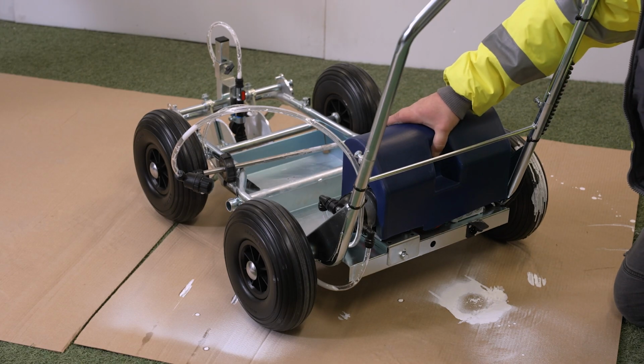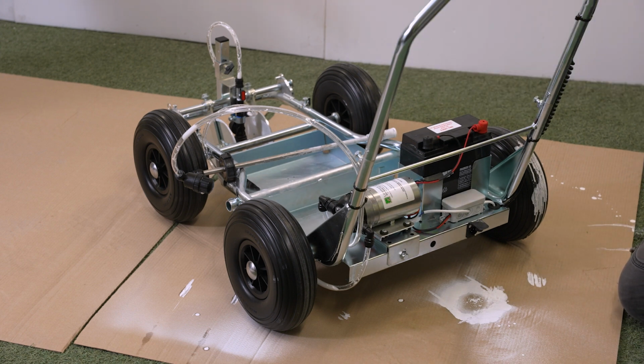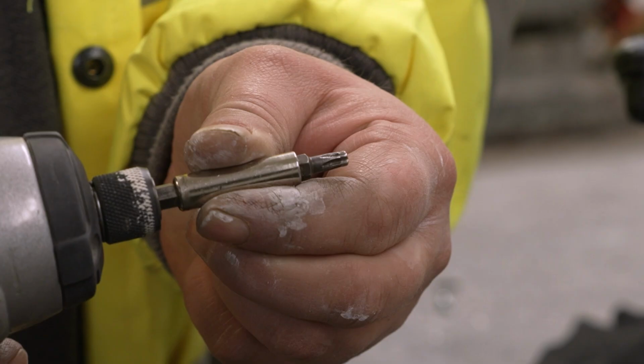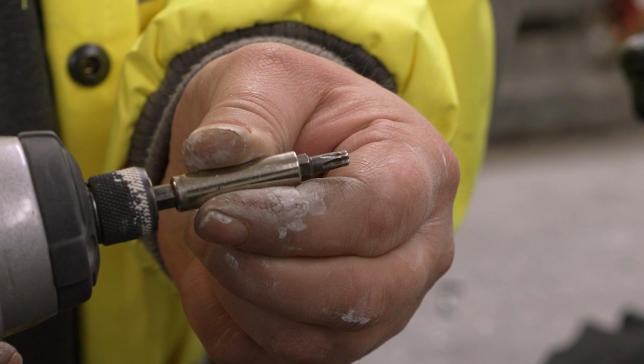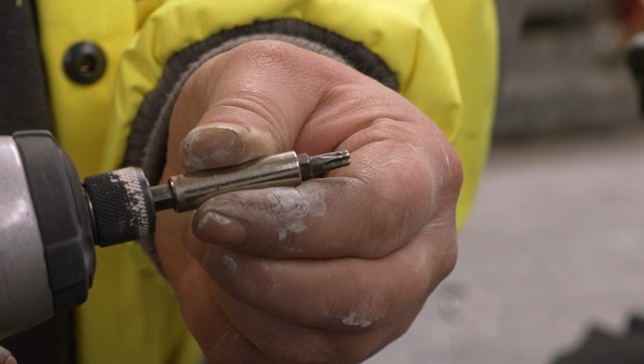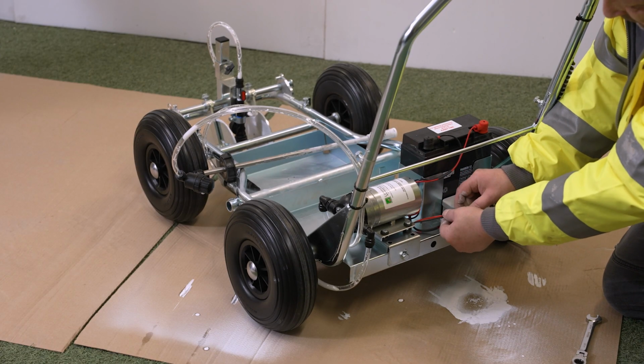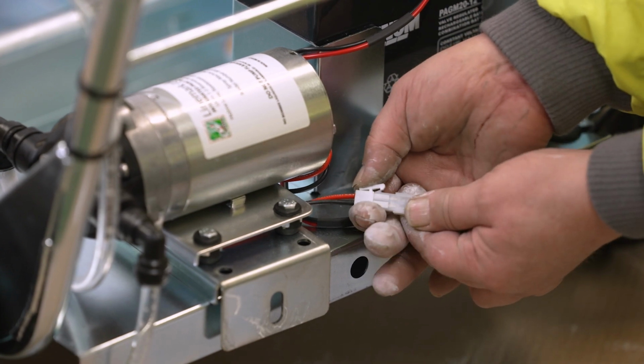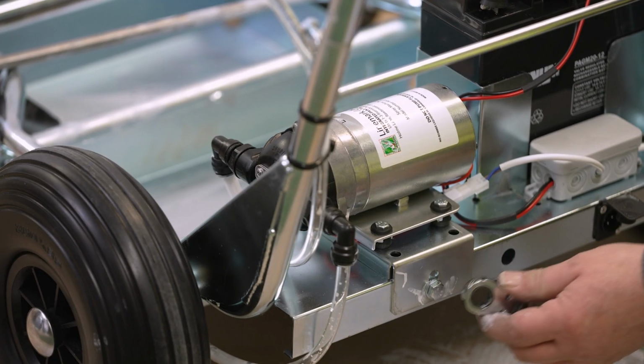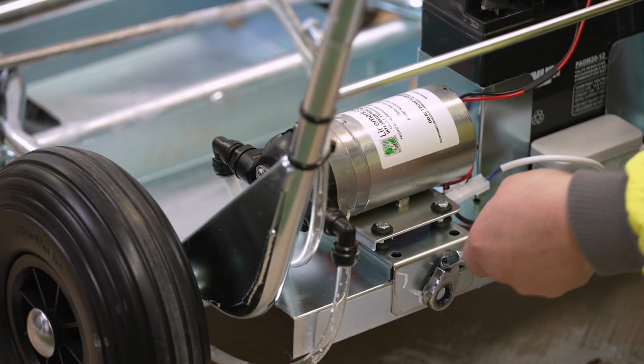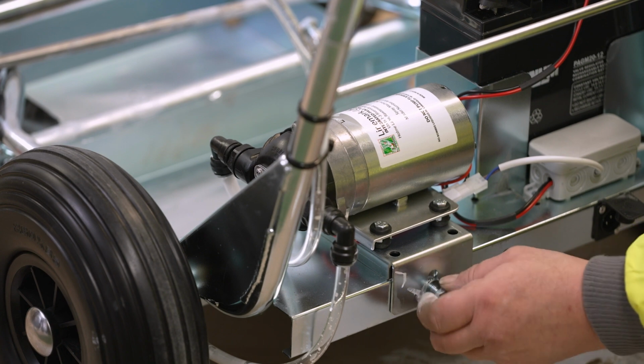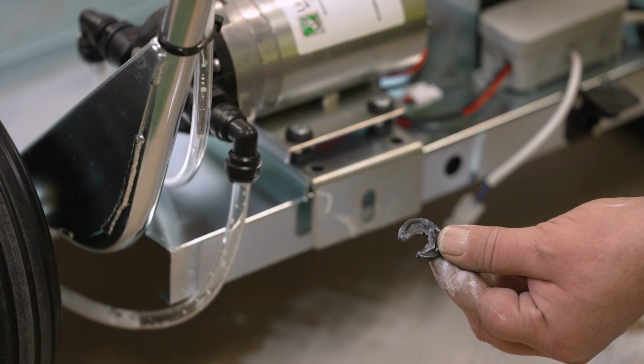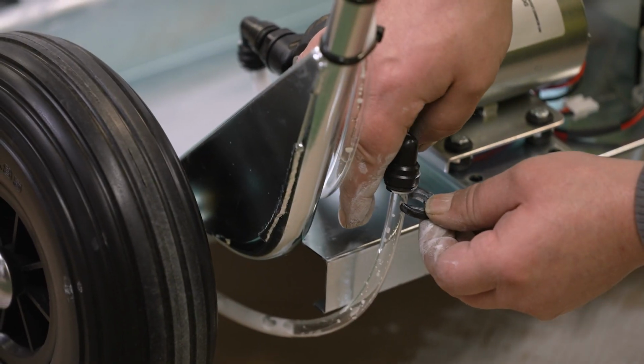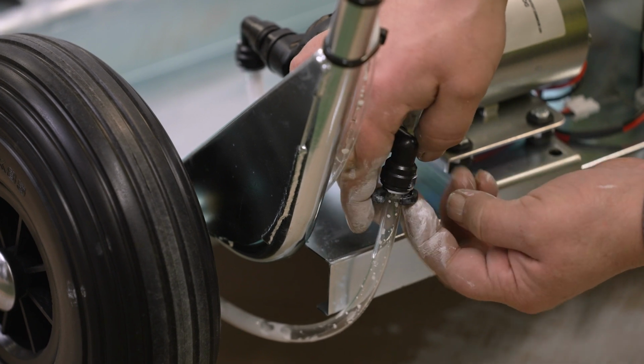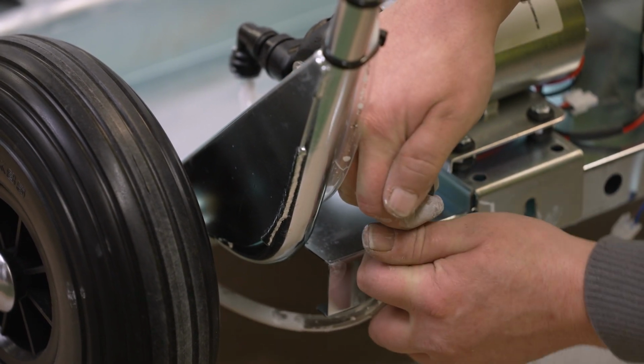The most important part of the service is changing the check valve inside the pump. This is done using a T25 torx screwdriver attachment for a cordless drill. First, disconnect the pump from the battery. Then, use a 13mm spanner to loosen the bolt which mounts the pump to the machine frame. Then you can use the release aid provided to help remove the plastic piping from the two connections to the pump.